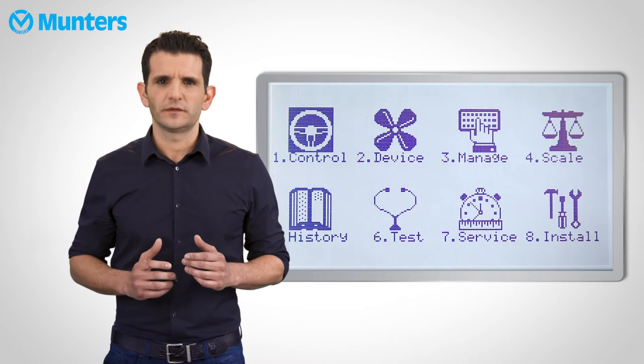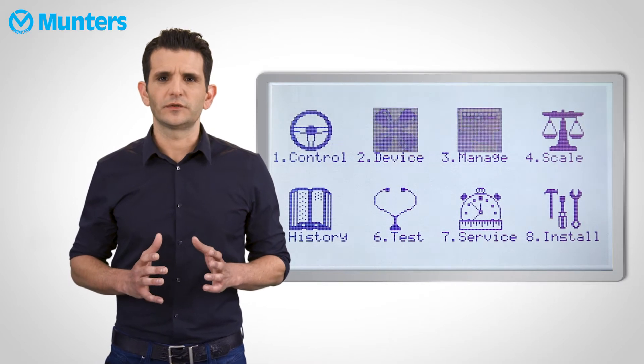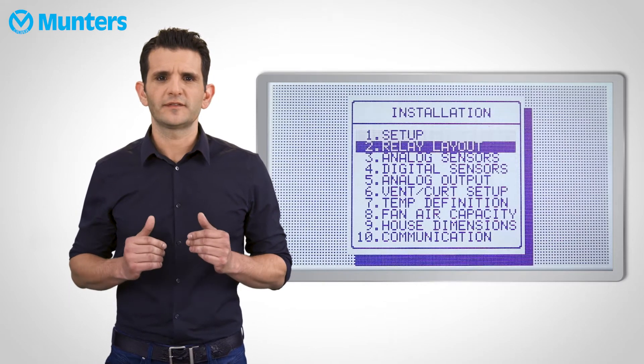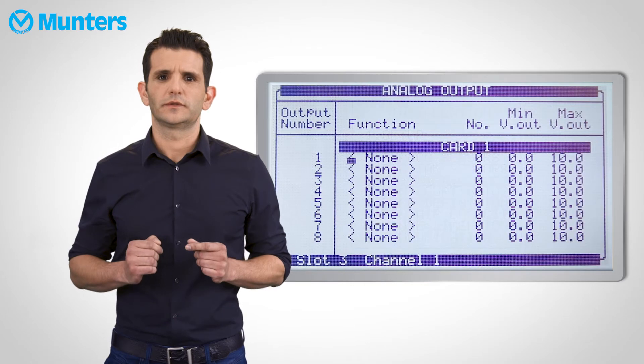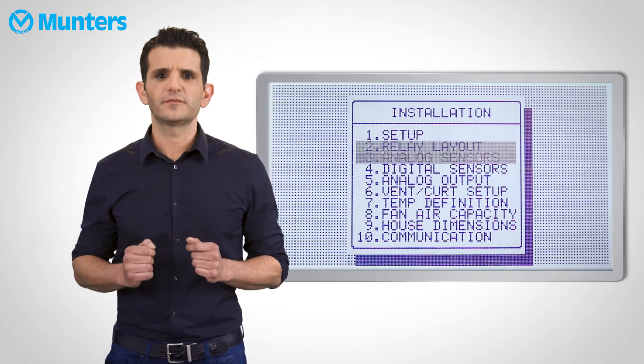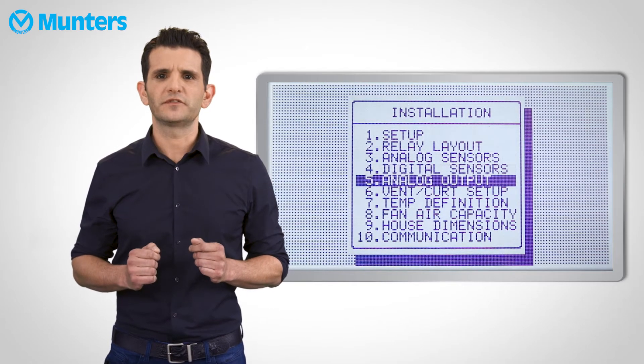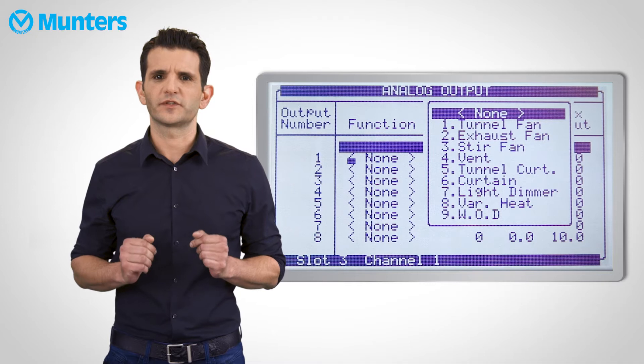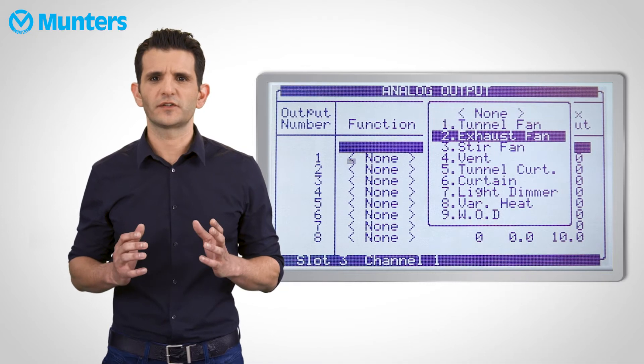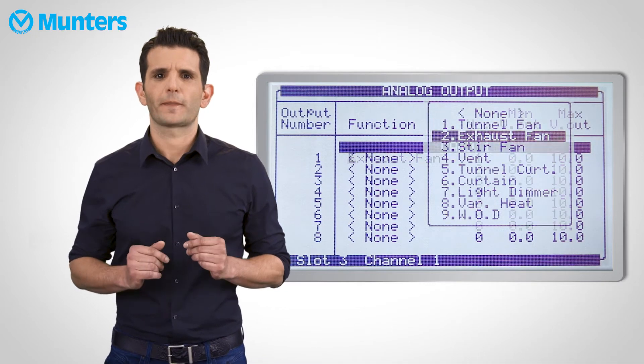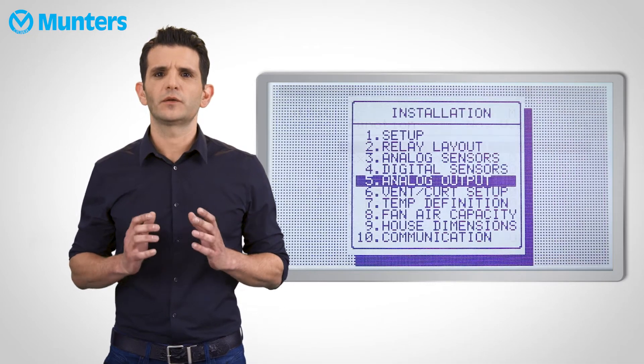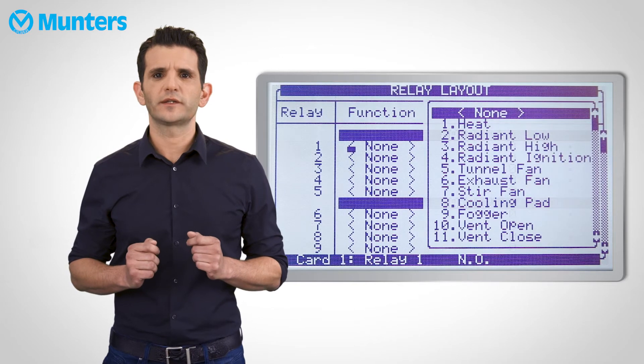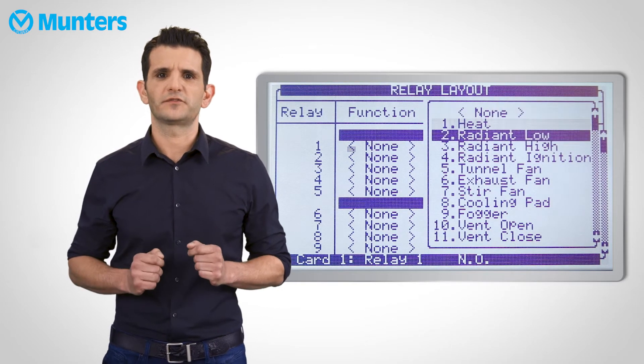Press Menu on the main screen, navigate to Installation menu, and then select Analog Output. In this menu, you can define any device as variable speed device. For example, Exhaust Fan 1. Now let's navigate back to the Relay Layout and try to define an exhaust fan.